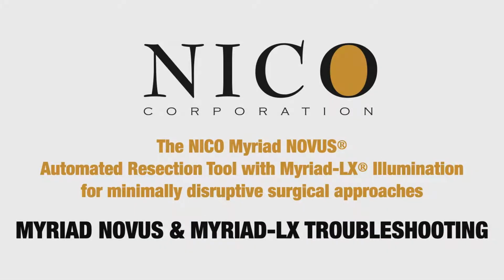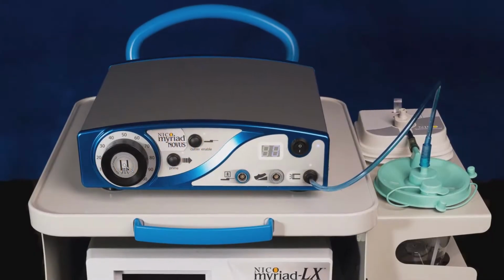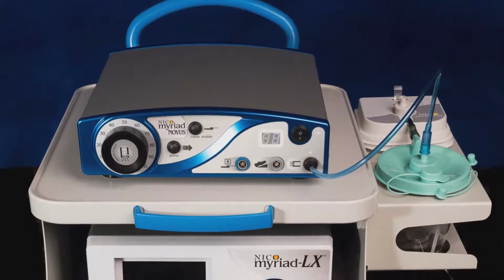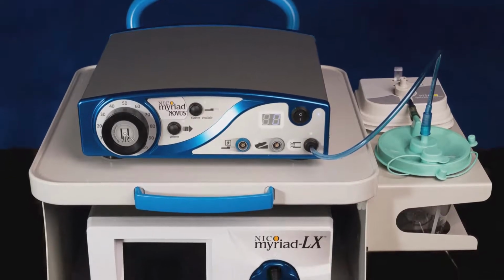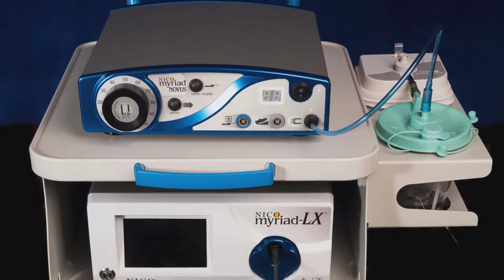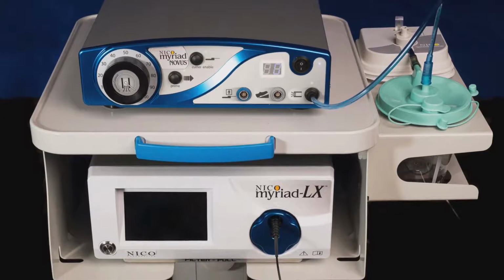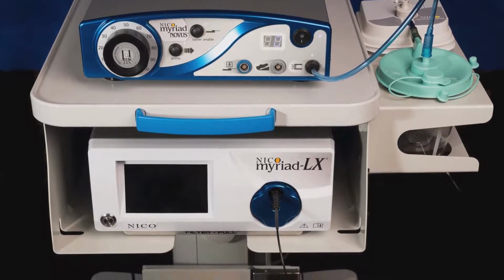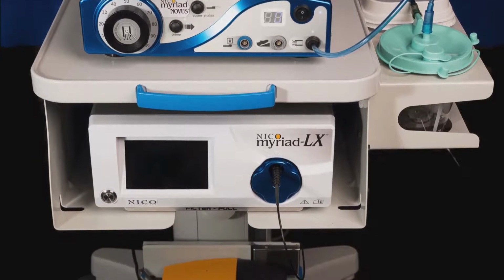Myriad-NOVUS and Myriad-LX troubleshooting. The Myriad-NOVUS console and Myriad-LX light source should ideally be placed at the foot of the patient, at waist level, and maintain a 5-foot distance from any electrosurgical equipment.